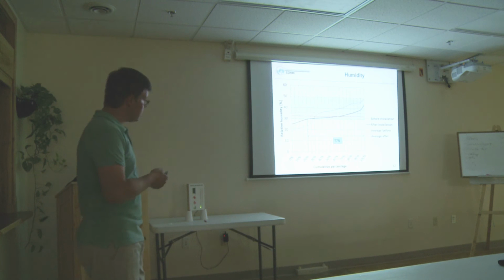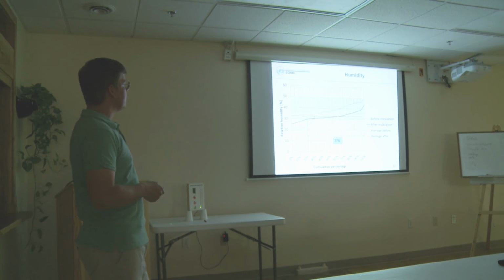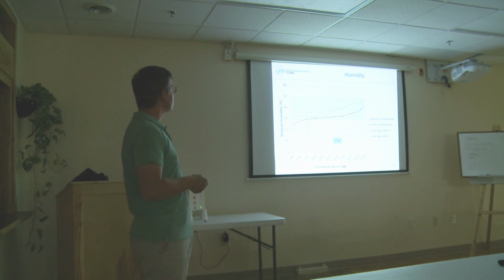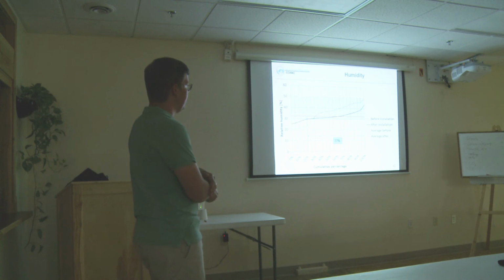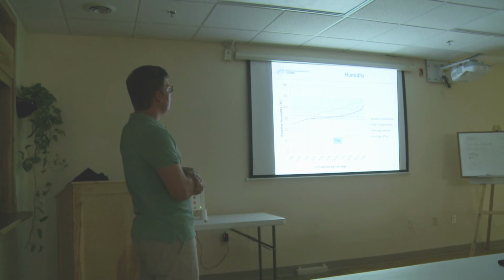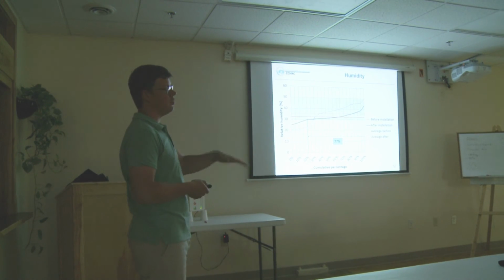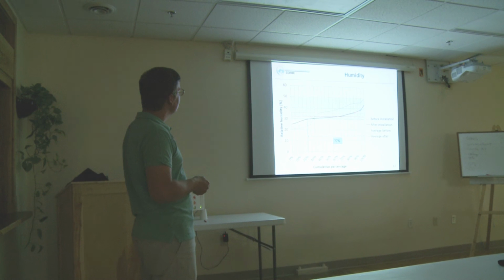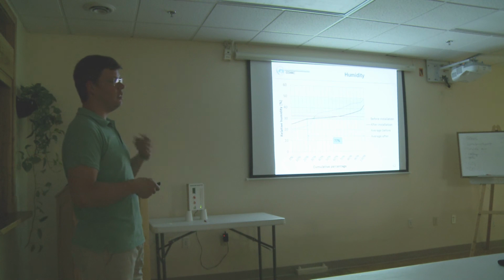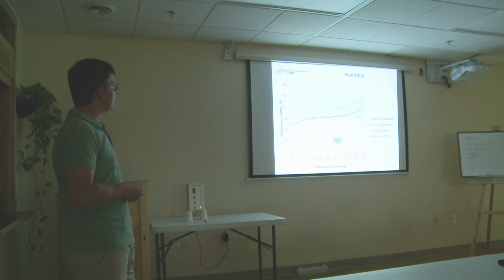Also the humidity was a good finding. Before, humidity was not an issue either—it was below 50% the whole time we measured. We were curious how it would change when we installed the ventilation. We expected it to drop a lot, but it didn't. For 77% of the time, it stayed within the 30 to 50% range. It was actually higher than before because the lower end got higher, and we think that's due to the moisture recovery ability of the wheel—some of that moisture shifted up a bit, so that couldn't be better.